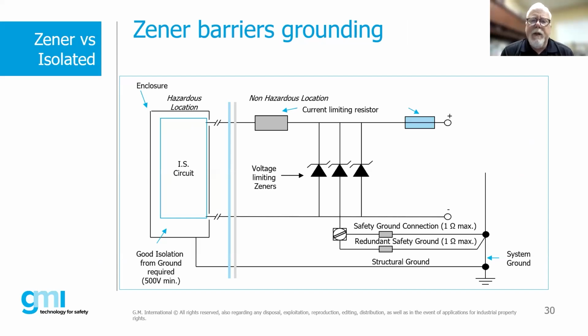Now, how do we ground Zener barriers? In many cases, you'll notice that we actually have 2 different ground connections. This is not a requirement by the standards, by the way. This is more or less what is typically done in industry. They'll have a safety ground, and then they'll have a redundant safety ground. The reason is that, at times throughout the life of the installation, you're supposed to go back in and check how reliable this ground is. Well, if this is in service and we want to disconnect any ground, then all of a sudden we've taken the protection concept potentially offline. So a lot of times they'll have 2 connection points for our IS barriers, and that's strictly just to be able to test the quality of the ground as time goes on. So that's why you see that. Maybe sometimes you might even see a specification being called out for that. That's generally the reason why.